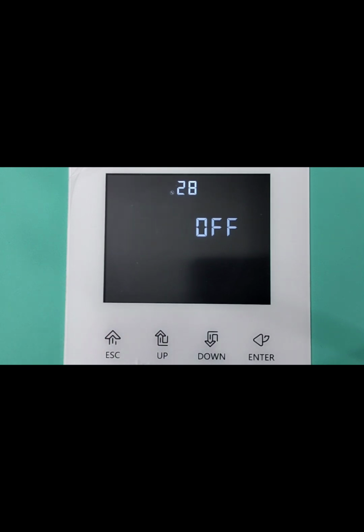Option 28. Missing battery alarm. If you are using without battery, you can disable this. Option 29. Equalizer setting. Equalizer voltage point. Equalizer charging point. Equalizer delay time. Equalizer interval settings. Turn on the equalizer immediately.